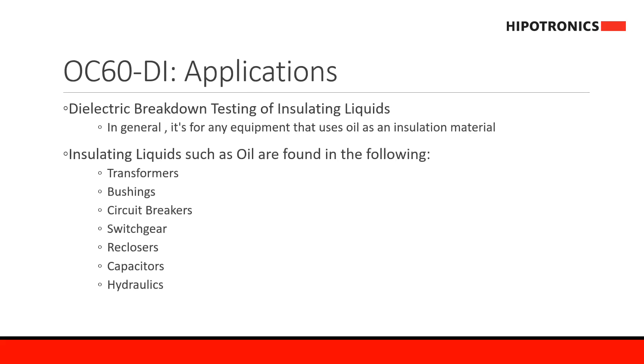The OC60 DI is used to perform dielectric breakdown testing on insulating liquids, most commonly oil. Essentially any equipment that uses oil as an insulating liquid will need to have that oil tested. This type of equipment includes transformers, bushings, switchgears, capacitors, hydraulics, circuit breakers, and reclosers.